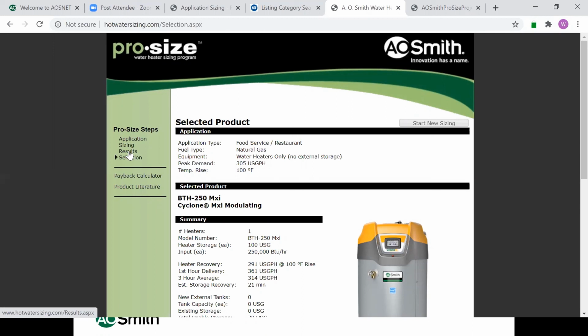I'm using my hand sprayer, which those documents that I was telling you about restaurants, which you're going to share there, they tell you that a pre-rinse hand sprayer assume 45 gallons per hour. And that's not something that A.O. Smith made up. That's based off of ASHRAE sizing principles.